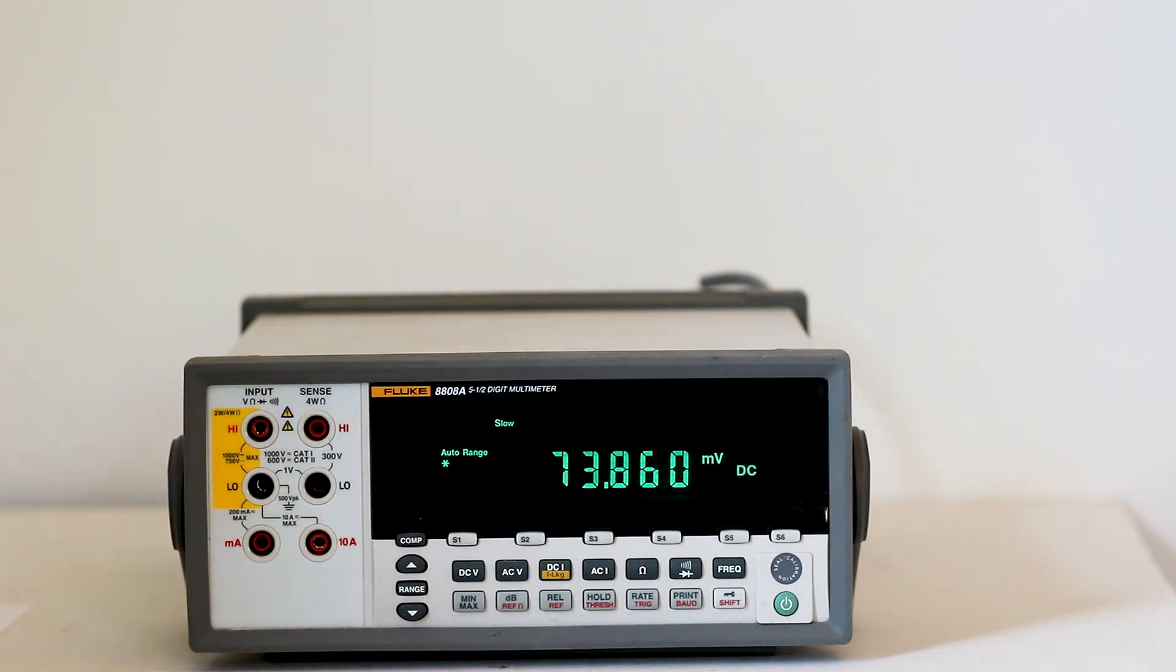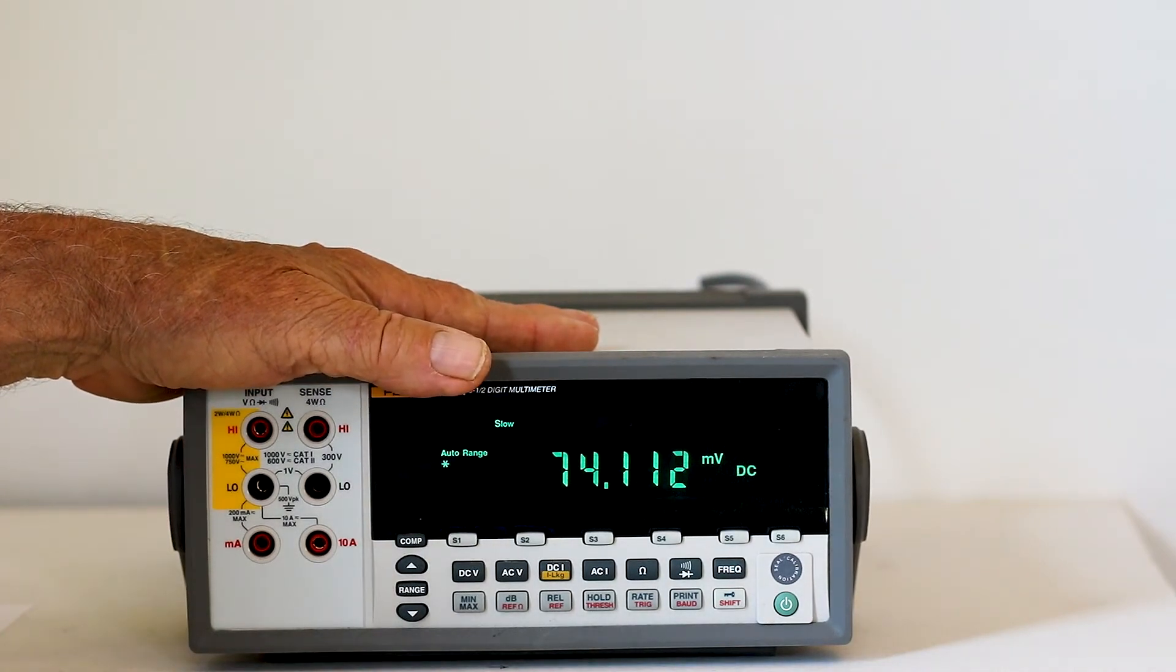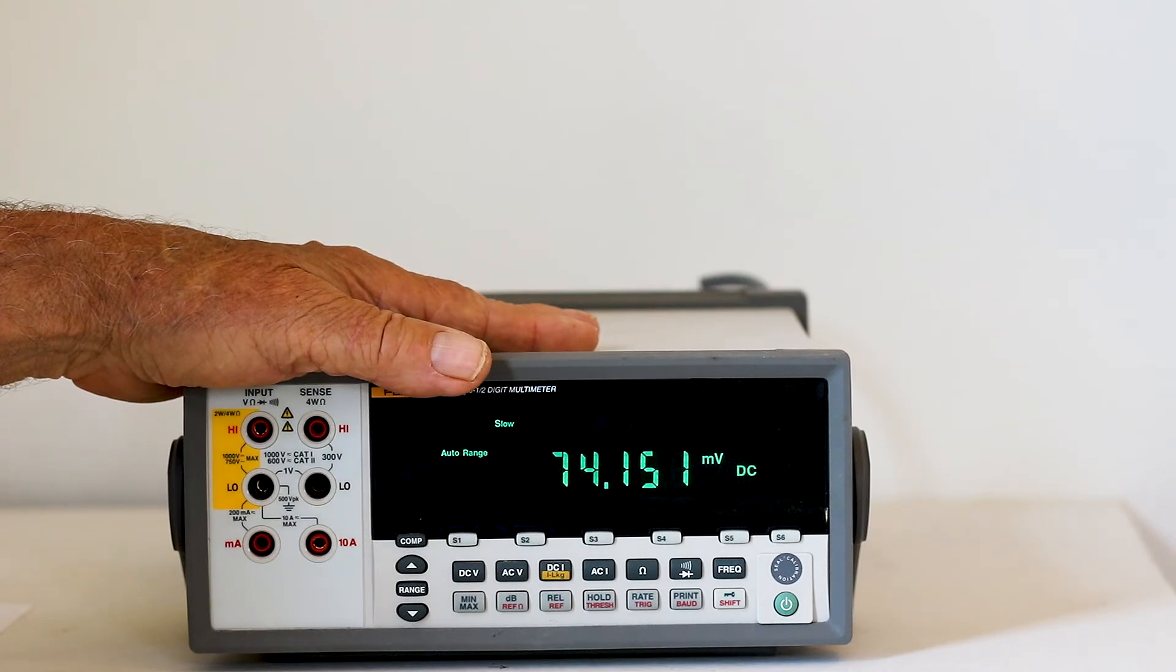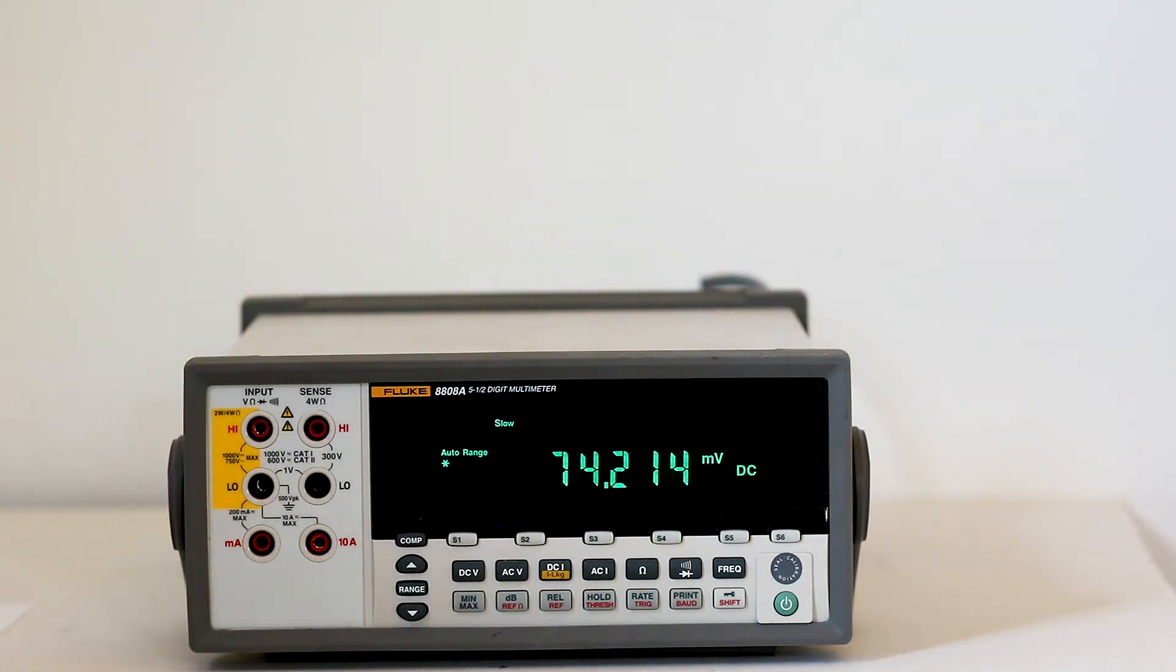Another Fluke multimeter that is useful in the shop or lab is the 8808A five and a half digit bench type digital multimeter. It has many useful features, as in the Fluke 287 handheld multimeter. With 5.5 digit resolution and up to 0.015 percent accuracy, this Fluke bench multimeter has sensitive DC leakage current ranges, front panel setup keys and the TL 2x4 wire measurement capability, which enables accurate low resistance readings using just two leads.